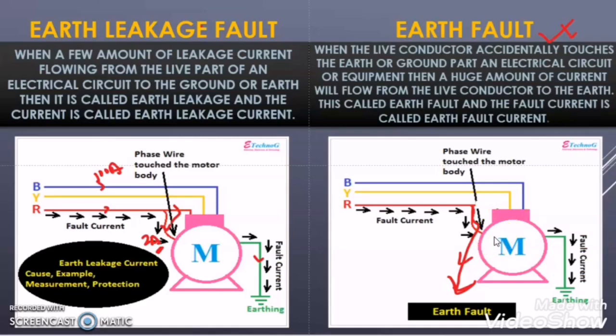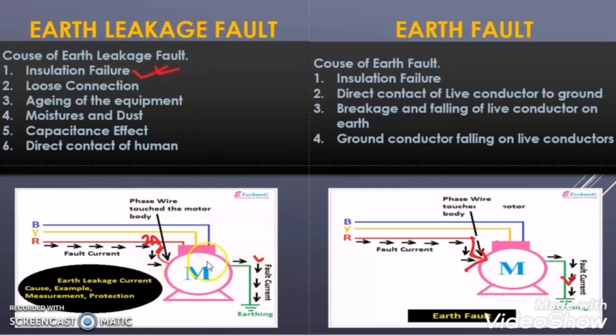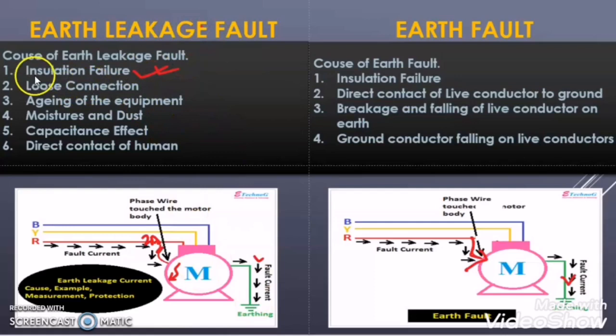Now let us try to understand what are the different causes of earth leakage fault and what are the different causes of earth fault. So the first cause of earth leakage fault is insulation failure. As we know the motor has windings and these windings have insulation. Suppose due to any reason like overload condition, some part of the winding insulation deteriorates and it is touching the body of the motor. That time the current will flow through the winding and from the damaged insulation point the current will pass to the body of the motor — this is the earth leakage fault condition. So the first reason is insulation failure.